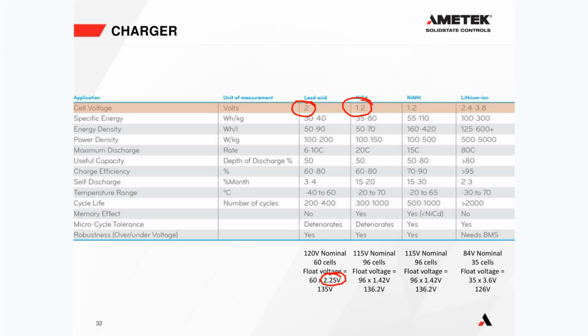NiCads, they say the nominal voltage of a NiCad cell is 1.2. Sometimes I've seen it say that the nominal voltage for NiCad is 1.0. But the charge voltage for NiCad is actually more complicated, because many manufacturers say that you should charge it at maybe 1.38 volts per cell until it gets to a certain point. And then you can charge it up to 1.6 volts per cell to get the energy back into it quicker and to overcome some of the losses in that cell.